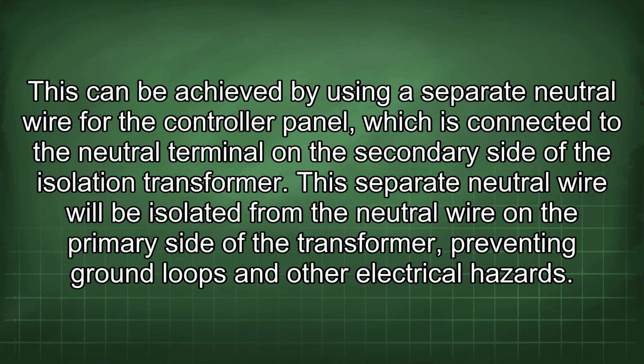This can be achieved by using a separate neutral wire for the controller panel, which is connected to the neutral terminal on the secondary side of the isolation transformer. This separate neutral wire will be isolated from the neutral wire on the primary side of the transformer, preventing ground loops and other electrical hazards.